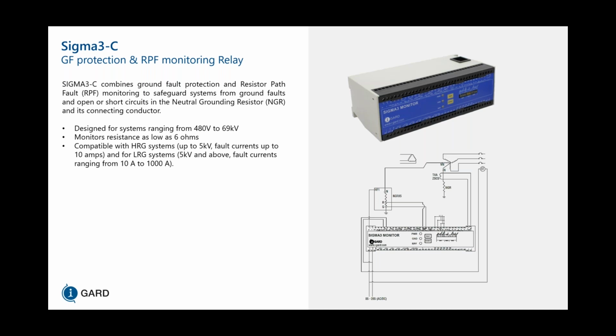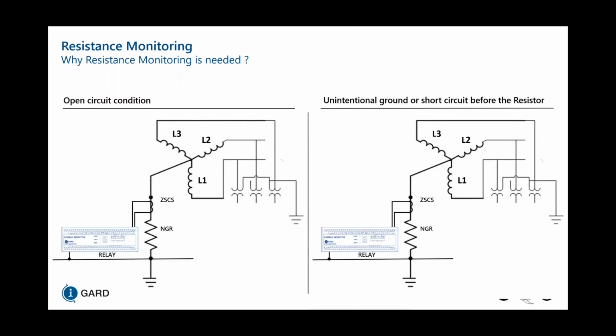So it's designed for systems ranging between 480 V to 69 kV. It monitors resistances as low as 6 ohms, and it's compatible with HRG systems up to 5 kV and fault currents up to 10 amps, and for LRG systems greater than 5 kV with fault currents that are greater than 10 amps up to 1,000 amps.